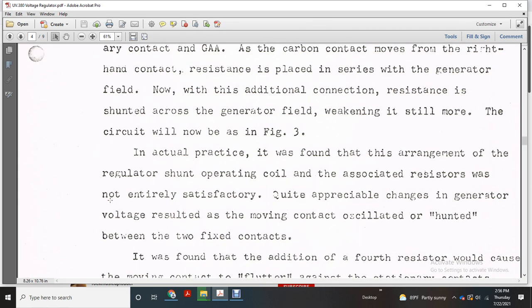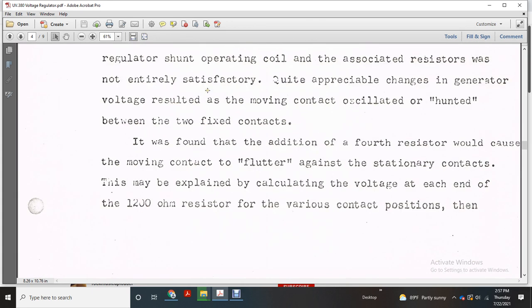In actual practice, it was found that the arrangement of the regulator shunt operating coil with the associated resistors was not entirely satisfactory. Quite appreciable changes in the generator voltage resulted in the moving contact oscillating between the two fixed contacts. It was found that the addition of a fourth resistor would cause the moving contact to flutter against the stationary contacts. This is explained by calculating the voltage at each end of the 1200 ohm resistor for the various contacts and positions.